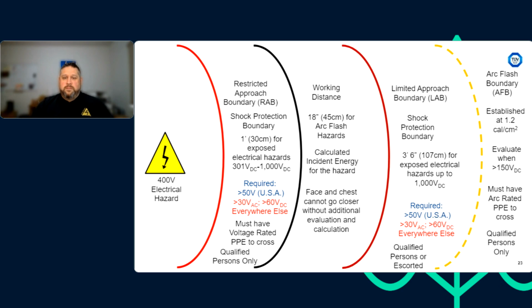So we have to do these calculations to verify that we're safe, and then establish the boundaries to keep other people safe. A limited approach boundary is just a shock protection boundary. It's basically, if you have exposed energized conductors, metal looks like metal whether it's energized or not. So if you didn't know anything about the system, you wouldn't know that that was a hazard. To keep people who are unqualified safe, we put up a boundary so that they don't accidentally go in there and touch something that's energized. That's all this is for.